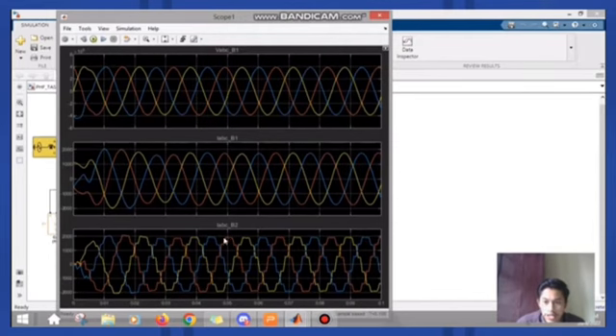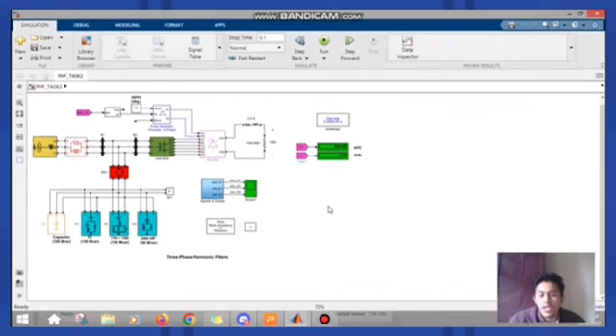The next one is current for B2. The current B2 shows a ripple waveform from the start to the end of the waveform. The highest peak of the current for B2 is 2.0 kiloampere. Next, we simulate the equivalent circuit by opening the breaker 1 here. When the breaker 1 is open, the filters here will turn into the deactivated condition. So we can find out the output waveform from scope 1 here.